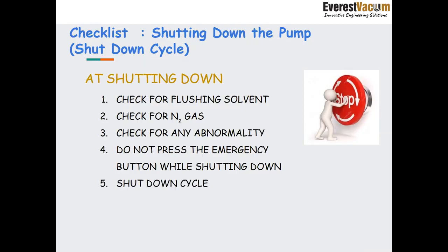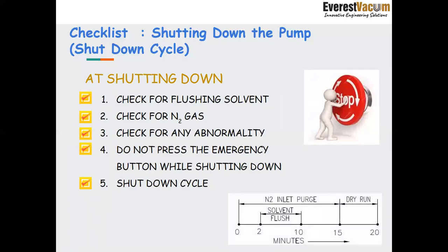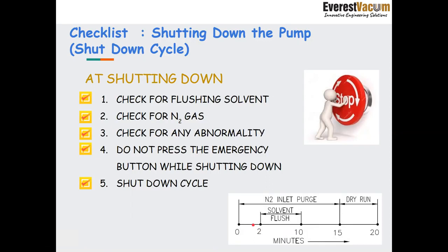Now I'll just brief you on what this shutdown cycle is about and how it looks. So this is the representation. On the x-axis, you can see the minutes. The cycle is a complete 20 minutes, so for 20 minutes this stop cycle will come into play. From 0 to 2 minutes, we are inserting nitrogen into the pump. The reason is that we want to break the levels of vacuum, because all the solvents that we would be using for solvent flushing would be very volatile. Their natural tendency would be to vaporize under the high levels of vacuum that this dry screw vacuum pump creates. So for these 2 minutes, it breaks the vacuum.